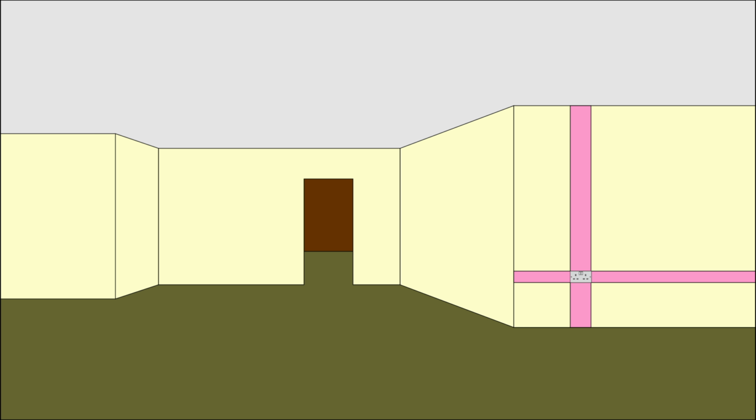Now of course those are all very well, but those don't really help you get wires to sockets, switches and other equipment, so the next part of it is that wherever you're installing a piece of equipment, so a socket in this case on this right hand side wall, the fact of placing a socket there and connecting wires to it will create two zones, as we've shown here, a vertical one and also a horizontal one. And provided that the cables are actually connected to the item on the wall, so that would be the socket in this case, you can put those cables in anywhere in that pink area, so say vertically above and below the socket, and to the left and the right as well.